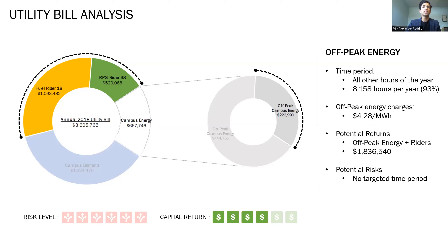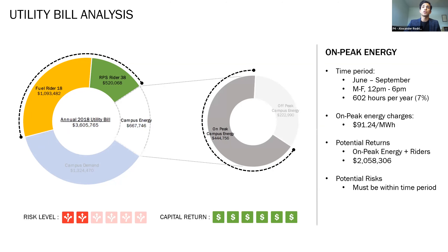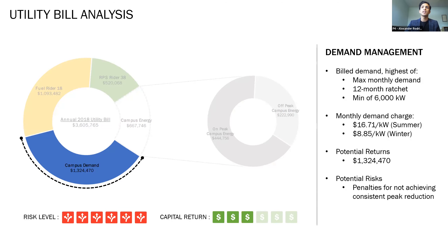To evaluate savings opportunities for the off-taker and in turn warrant a higher PPA price, three main strategies were studied: on-peak energy reductions, off-peak energy reductions, and demand management. Off-peak energy charges stipulate a rate of 0.4 cents per kWh, and targeting off-peak energy combined with non-time-dependent cost riders could yield a maximum return of $1.8 million. As there is no targeted time period, this strategy poses no potential cost savings risk to NMSU. On-peak energy charges are in effect Monday through Friday, 12 p.m. to 6 p.m., June through September, and stipulate a rate of 9.1 cents per kWh. Targeting on-peak energy combined with the cost riders could yield a maximum return of $2.1 million, though this strategy poses slight risk as savings must be achieved within this specific window. Demand charges are billed based on the highest of the max monthly demand, a 65% 12-month ratchet, or a minimum of 6,000 kW, and could yield a maximum return of $1.3 million. However, this strategy carries the most risk as consistent peak reduction must be achieved to ensure monthly savings.